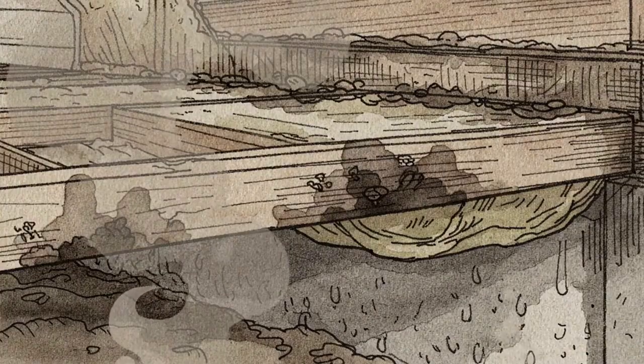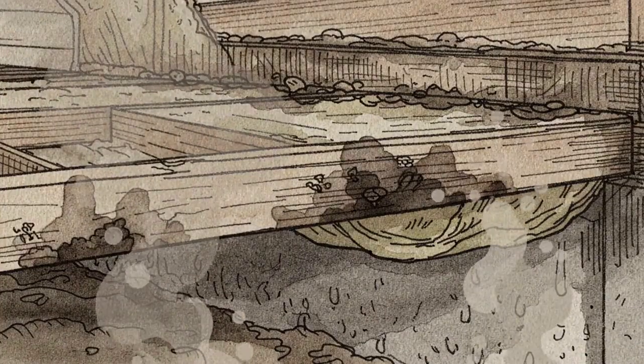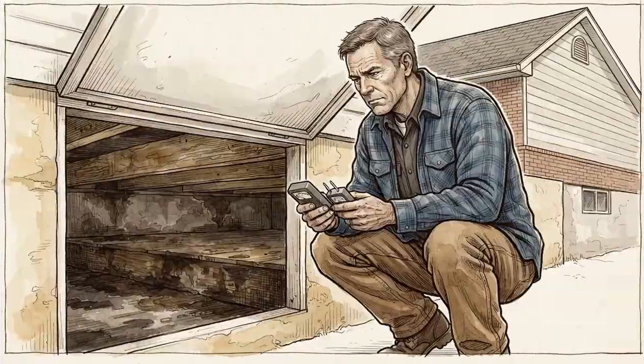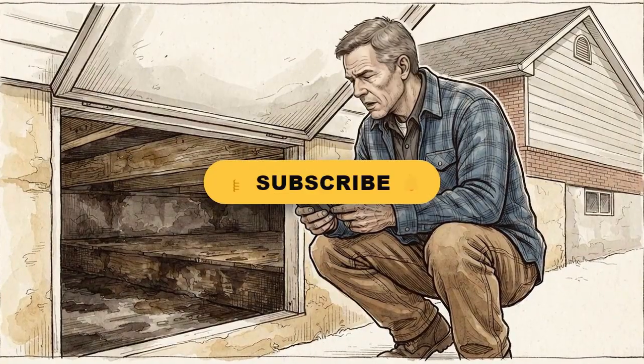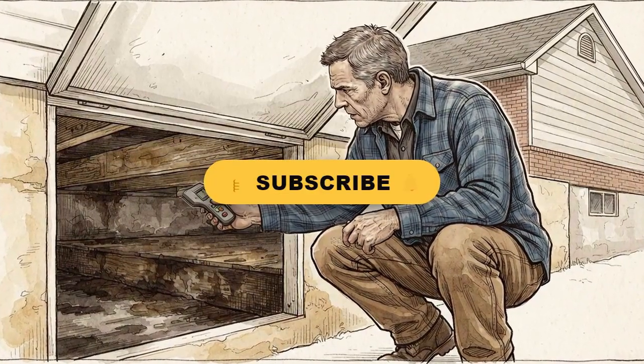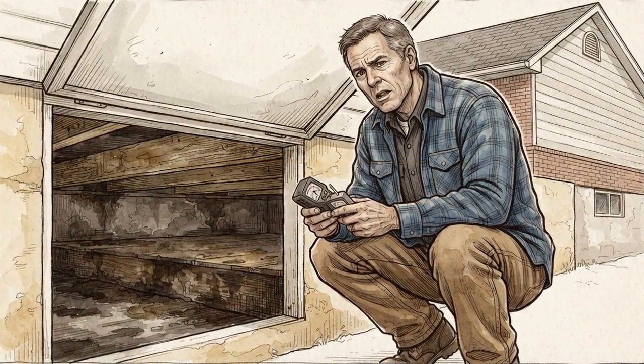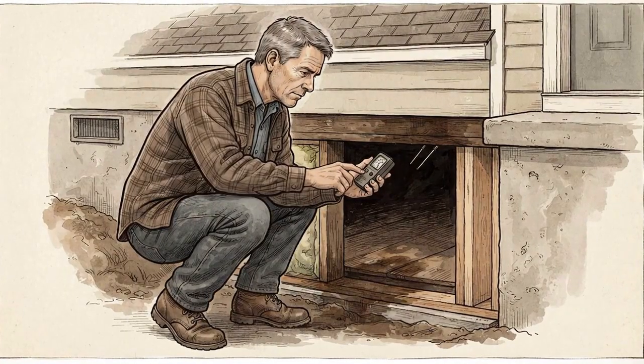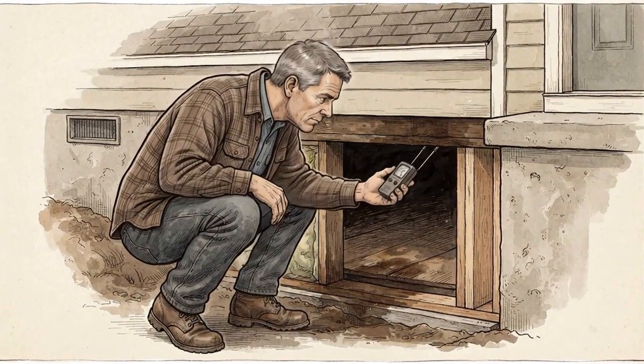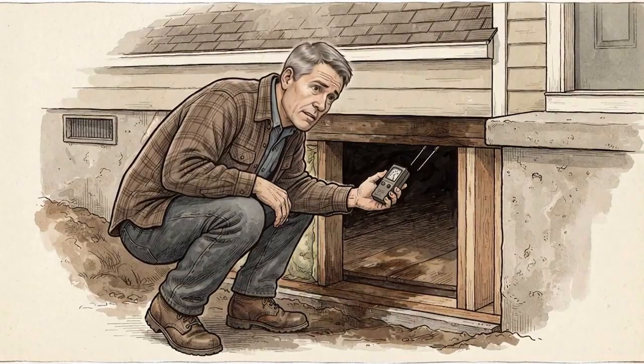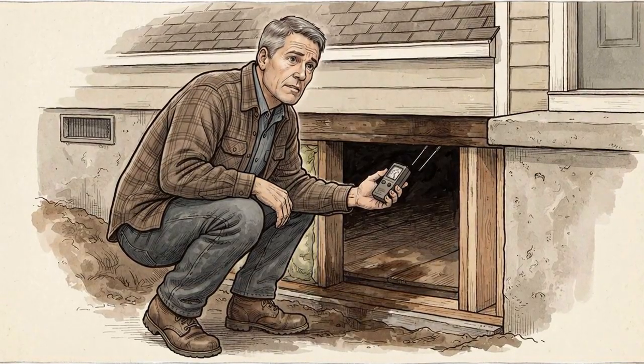According to Building Science Corporation diagnostic protocols, if the crawl space reading is more than 5 percentage points higher than the outdoor reading during summer months, you have confirmed net moisture addition. The ventilation system is adding humidity, not removing it.